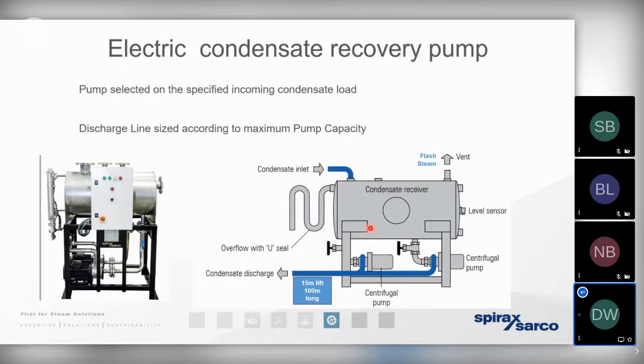And of course, we run the risk then that we're never able to cool the condensate down sufficiently before it's passed across those pumps. So please give thought to ensuring that that receiver is sized, as is the vent size, correctly. And similarly, it's not good working practice to lag the receiver, as we need to ensure that the condensate cools down slightly before it is taken away across the pumps.